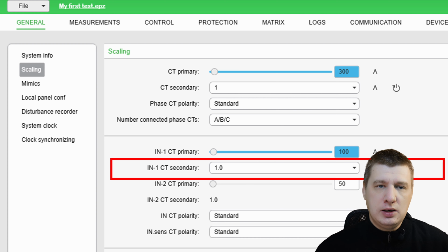Increased sensitivity. Earth fault current in a highly impedant network can be tiny. A 1 amp secondary rating allows the relay to detect much smaller primary current than a 5 amp rating. A 1 amp circuit has much lower electrical resistance, or burden, on the CTs and the P5. This keeps the measurement highly accurate without overloading the transformers. If your earth-fault CT is located far away from the relay, the 1 amp signal travels much better over long wires with less energy loss.